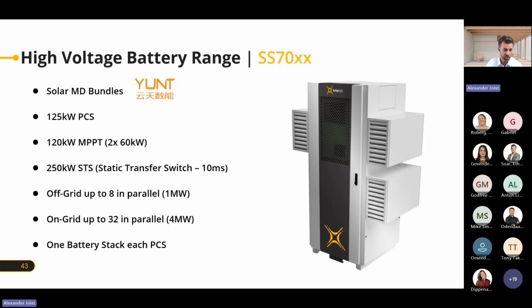And what you can do, for instance, is have the PCS on this side, right? And we have the MPPT here, or the other way around. The other way around would have been better. Sorry, the other way around is actually much better, just from the AC and DC side, but it's fine. And then the STS on the bottom here. And then you can connect, and then you have a full hybrid solution in one system with 125 kilowatt PCS, 120 kilowatt MPPT, so it's 2 times 60 kilowatts, and a 250 kilowatt static transfer switch with a 10 millisecond changeover time. So quite a nice solution.